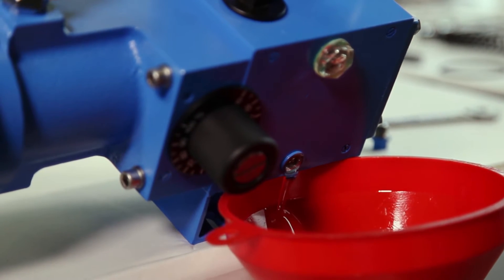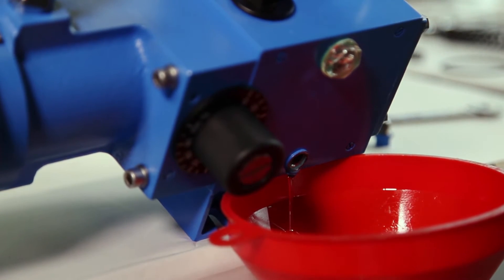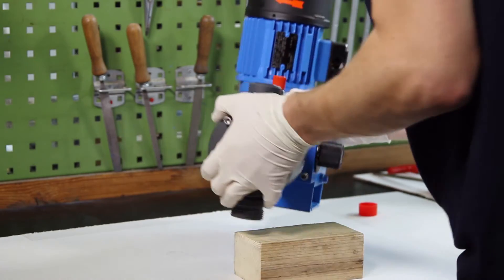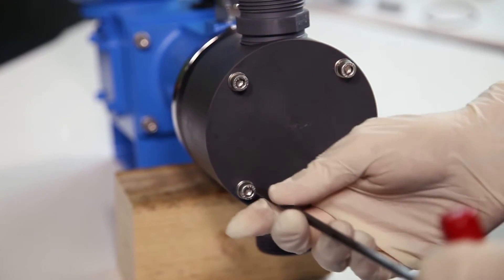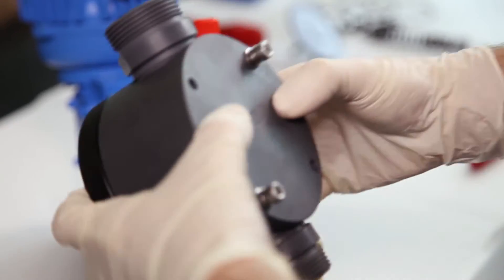Make sure the pump doesn't fall off your base while you tilt the pump. Next, the dosing head and the diaphragm can be unscrewed. The piston flange should be positioned higher than the drive gear to prevent residual oil from running out. The dosing head and diaphragm can be taken off after all screws are undone.